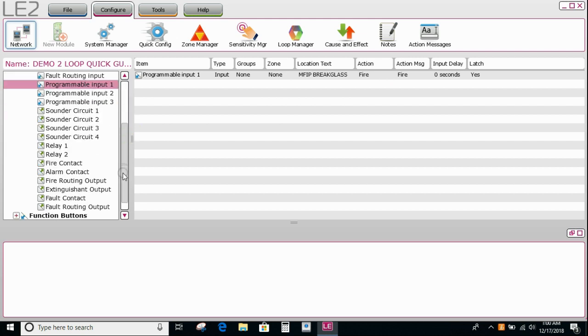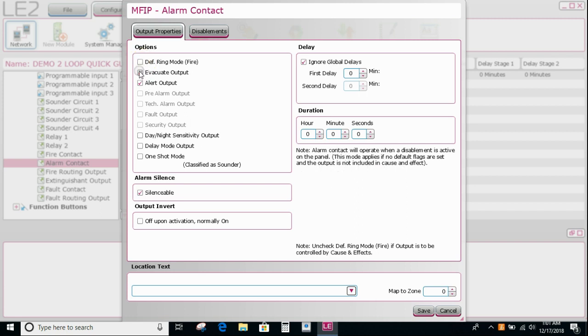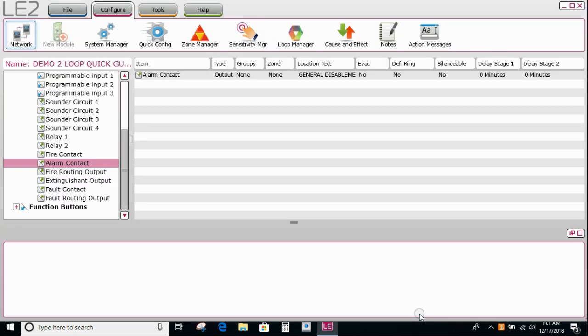The next thing I might do is my general disablement output for my ASC. And that's always done from Taktis from the alarm contact typically. It's the only one that can by default be set up as a general disablement, as this note here suggests. If we untick all of these, including the silenceable, this now becomes a general disablement output typically to ASC. I'm going to say save. So that's our output set.